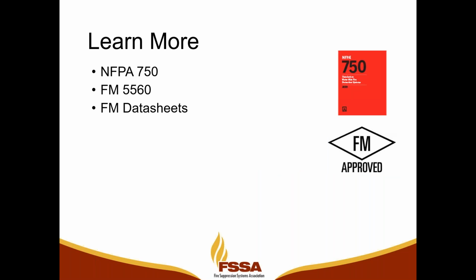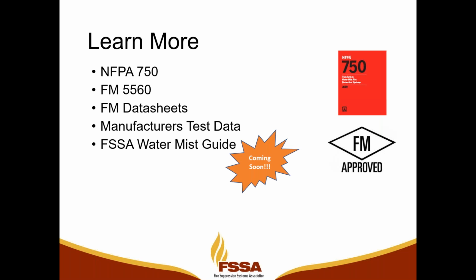Yeah, so NFPA 750, if you want to learn more, I would encourage you to read NFPA 750 cover to cover. It'll tell you everything you want to know about water mist. It'll send you down a rabbit hole of references to other NFPA standards. FM 5560 talks about the test protocols that we follow and some design principles. And then you can find an FM data sheet for every hazard that will give you very specific guidance. Manufacturers' test data and manuals are other great sources of info.